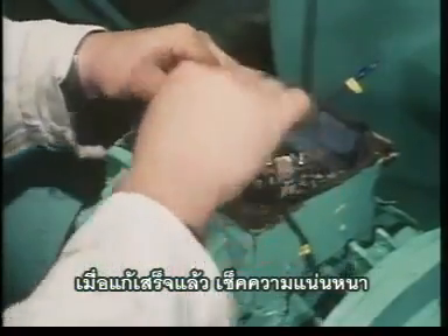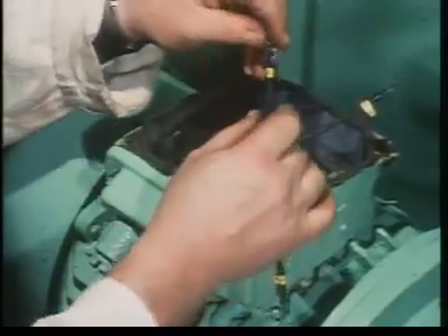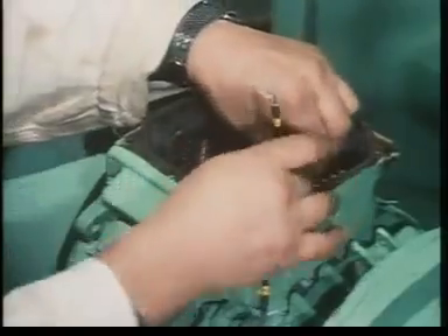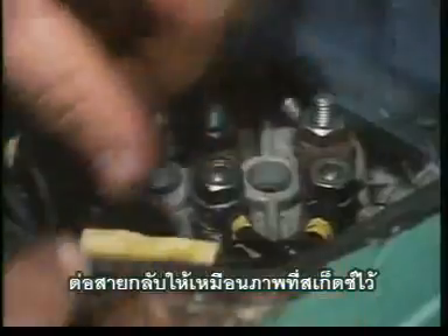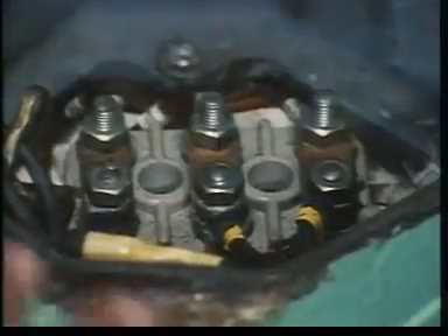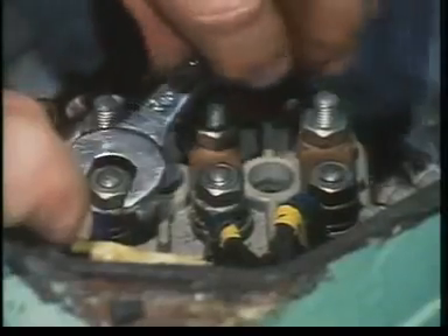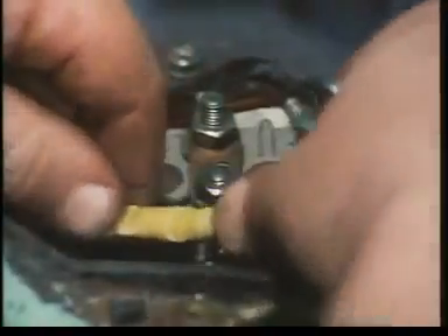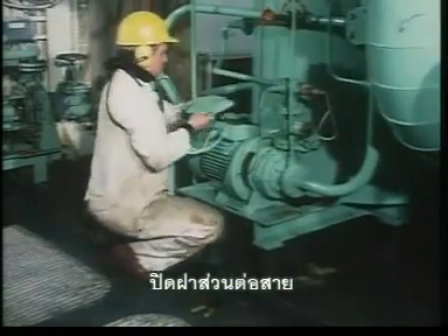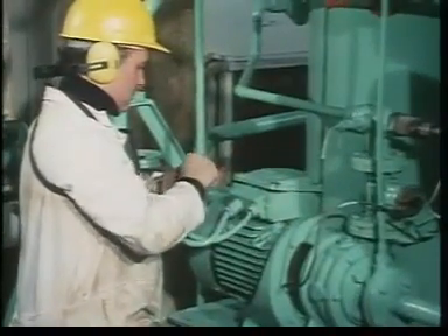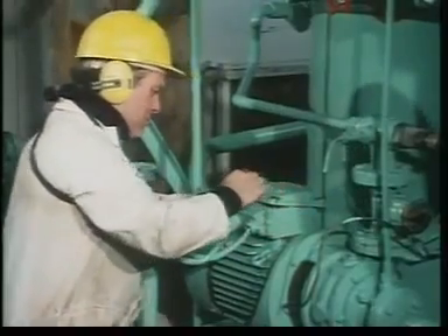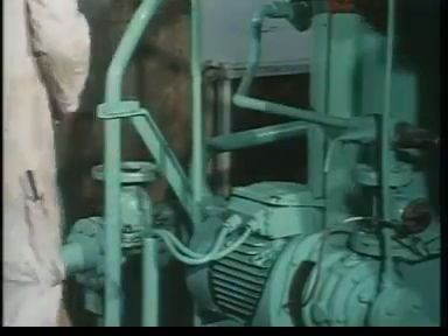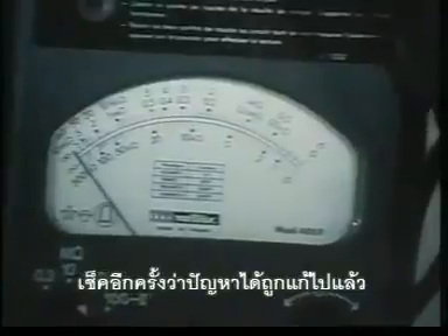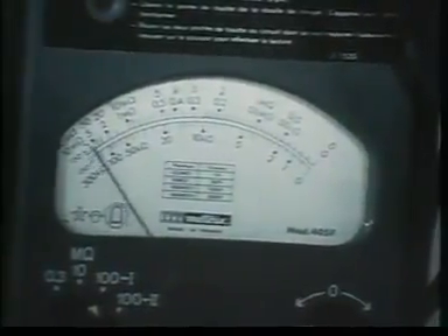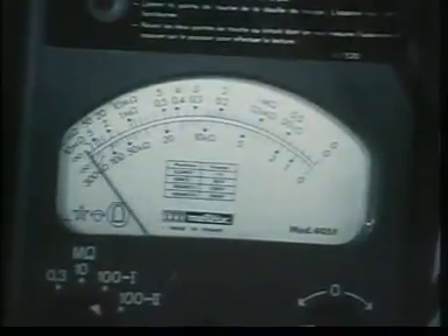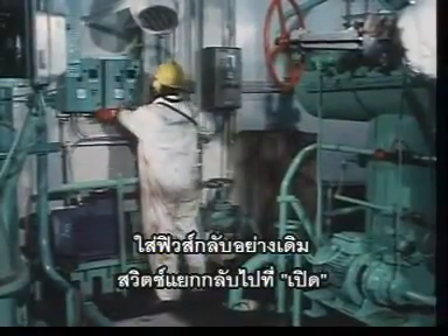Having completed the repair, check the joint for tightness. Reconnect the cables according to your sketch of the connection and check that the nuts are tight. Replace the terminal box cover. Back at the starter, recheck the circuit to confirm that the fault has been eliminated. The fuses can now be replaced and the isolator switched on.